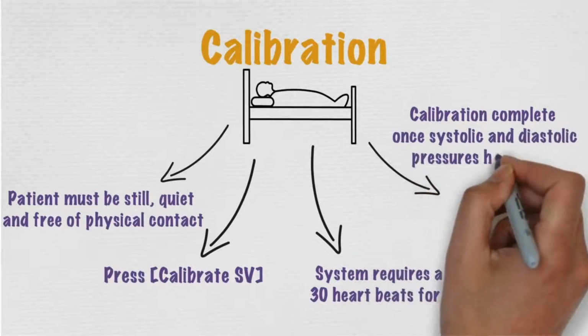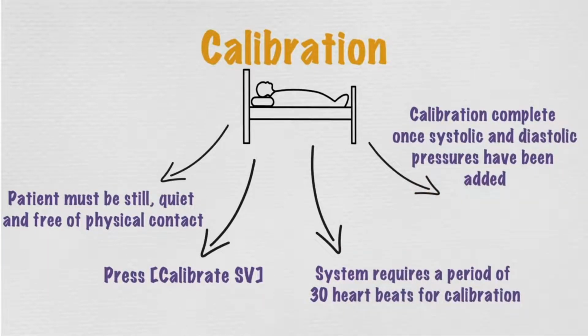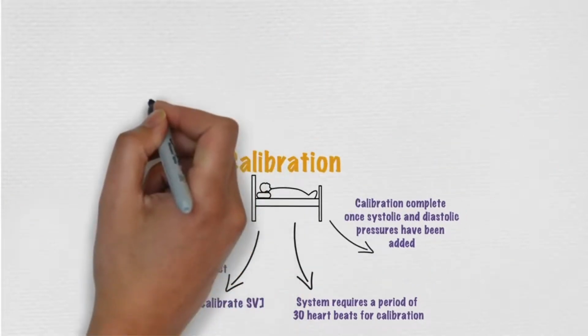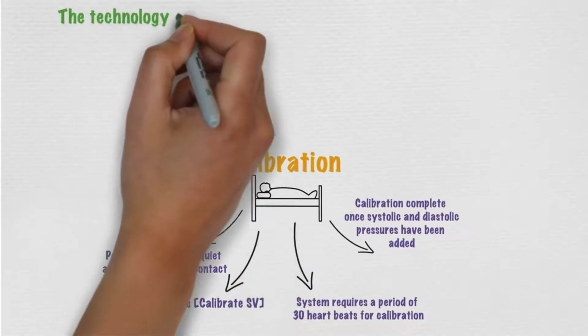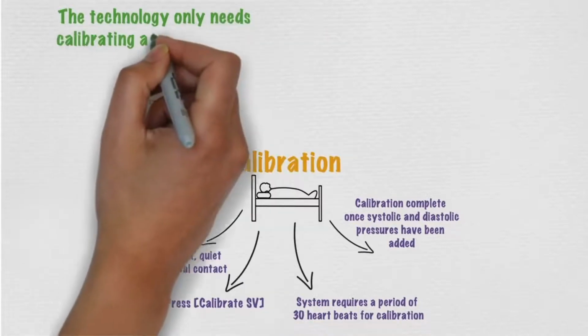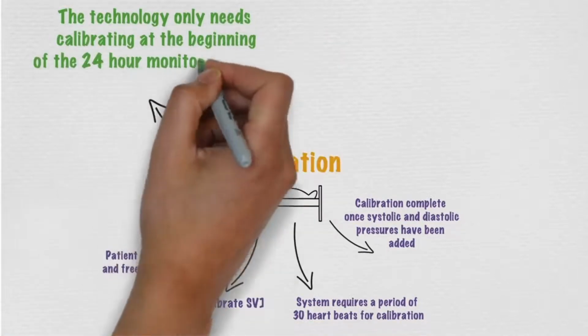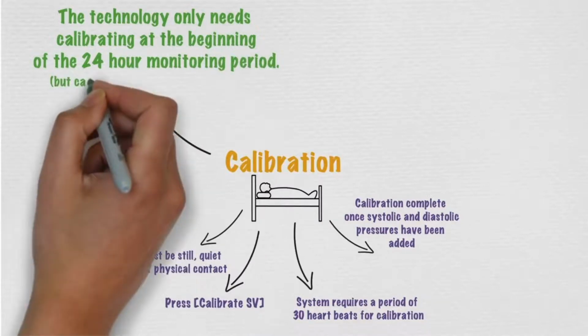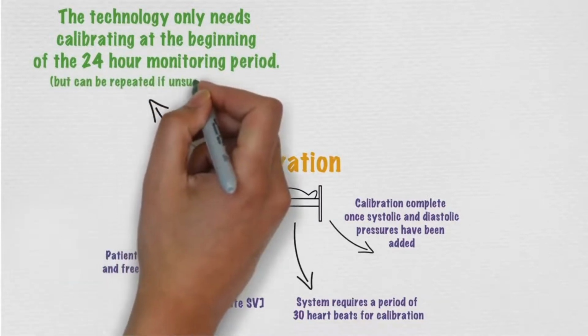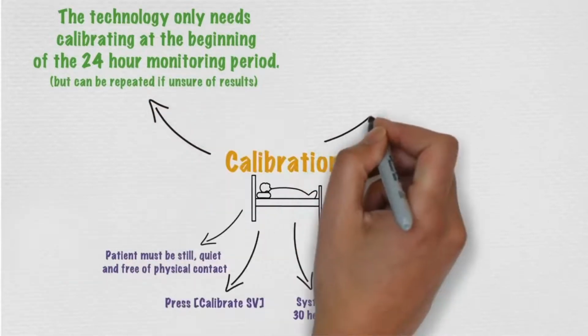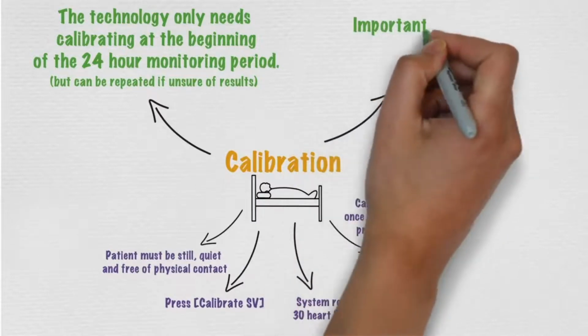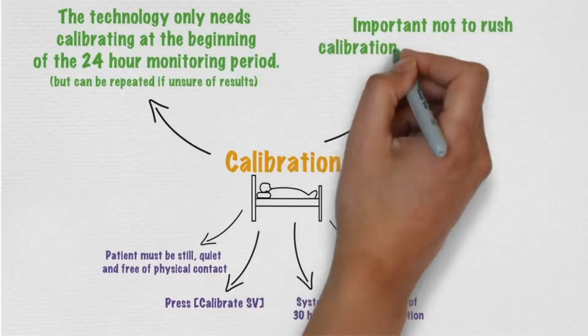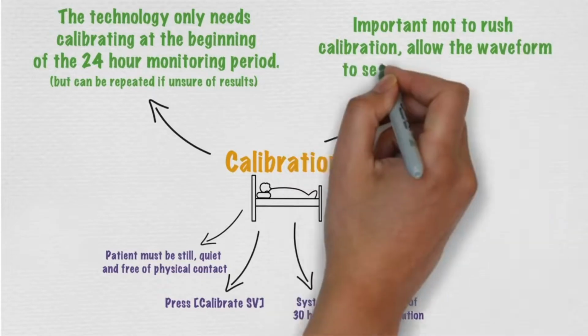If the patient has any arrhythmia, the average of 3 readings should be used. Note that the technology only needs recalibrating at the beginning of the 24-hour monitoring period, but it can be repeated at any time if unsure of the results. And it's also important not to rush the calibration. Allow the waveform to settle both before and after.